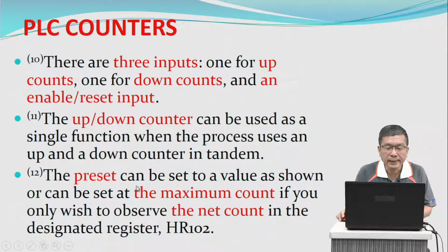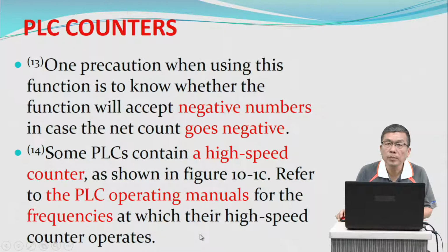The preset can be set to a value as shown, or can be set at the maximum count if you only wish to observe the net count in the designated register, holding register 102. One precaution when using this function is to know whether the function will accept negative numbers in case the net count goes negative.